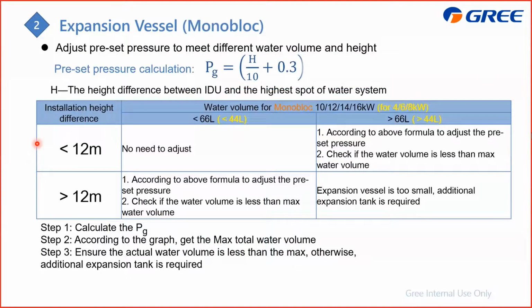And also you need to base it on the preset calculation, and adjust this for the best expansion volume. For the different expansion vessels, we also provide you this table, and according to what water system is installed on site, you can choose whether you need to add another expansion vessel or not. The step is first to calculate the PG, just follow this formula, and then according to the graph you can get the max total water volume. After that, ensure the actual water volume is less than this max, otherwise you need to add another expansion vessel.